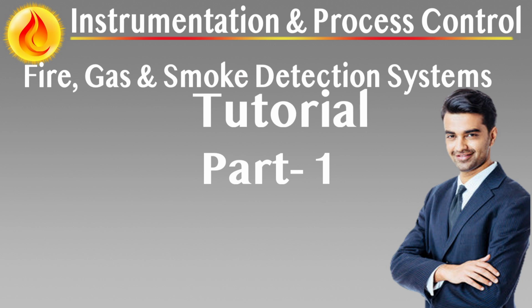Technology preference and application suitability. Infrared (IR) absorption detectors are the preferred technology for most point gas detection applications. They offer superior immunity to poisoning, rapid response times, and reliable operation in oxygen-deficient environments, conditions where catalytic detectors underperform or fail. Catalytic Pellistor-type detectors, although historically common, are now considered secondary and require principal approval before use. They measure gas concentration by oxidation, which produces heat detected via a Wheatstone bridge. This method is slow to respond, 20 to 30 seconds, requires oxygen to function, and is highly susceptible to poisoning from airborne contaminants like silicone vapors or lead compounds.